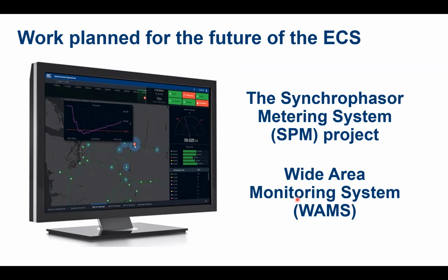But approximately 4 years ago, we had a need for a wide area monitoring system, which GSE intended to use to study the behavior of generators and to study disturbances in the 500 kV network. We started a project of installing PMUs, phasor measuring units, in order to implement a wide area monitoring system. And here we found out that we can use ECS relays since they are providing synchrophasor measurements. So half of the task was already fulfilled, because in half of the substations and outstations in the power plants where we have ECS relays and IEDs installed, we also automatically have the possibility of acquiring synchrophasor measurements.